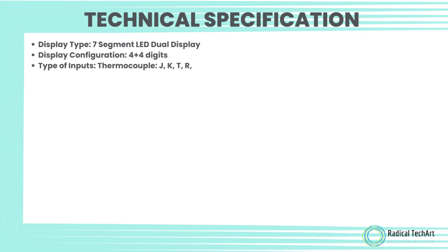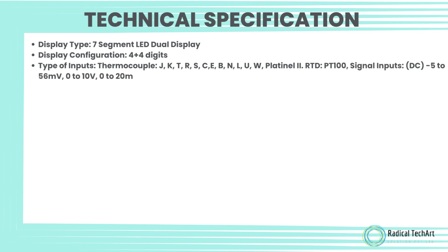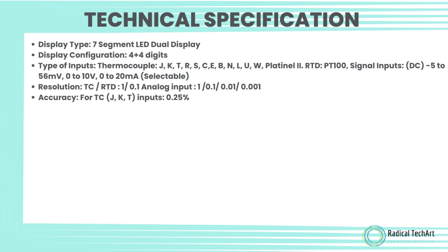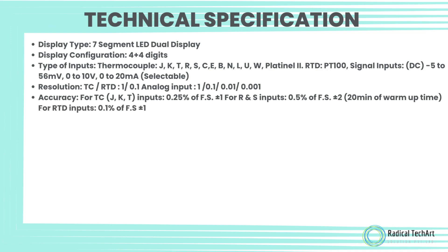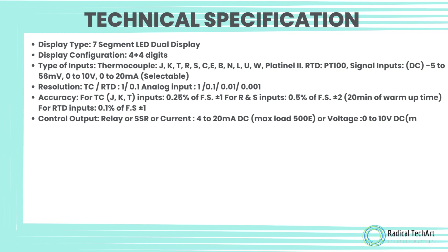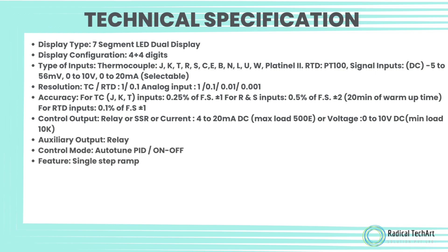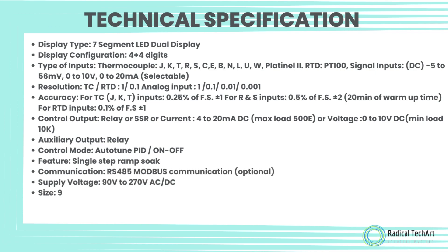Technical Specifications: Display type is 7-segment LED dual display, display configuration is 4+4 digits. Type of inputs: Thermocouple types J, K, T, R, S, C, E, B, N, L, U, W, Platinel II; RTD PT100; signal inputs DC: -5 to 56 mV, 0 to 10 V, 0 to 20 mA — all selectable.